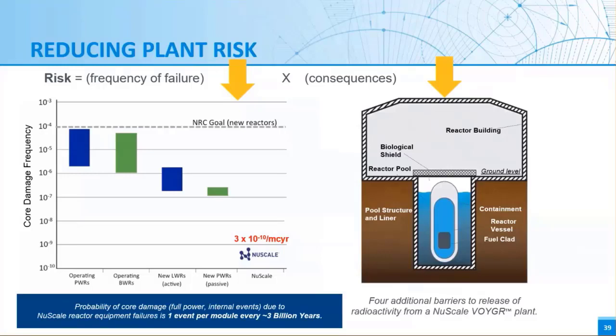This slide also shows on the right that there are four additional barriers to contamination release in the NuScale design. First, the reactor is below grade and submerged in the cooling pool, with no motive force needed to get the ultimate heat sink to the reactor. Second, it's underground with a stainless steel lined fuel pool. Third, the biological shield above the reactors. And fourth, the seismic category 1 reactor building with heating, ventilation, and cooling over the top of the reactors and their containments. So these are new barriers to release that don't exist in other plants. And as I mentioned, the containment vessel of the NuScale plant is about 10 times stronger than the containment of a conventional plant.